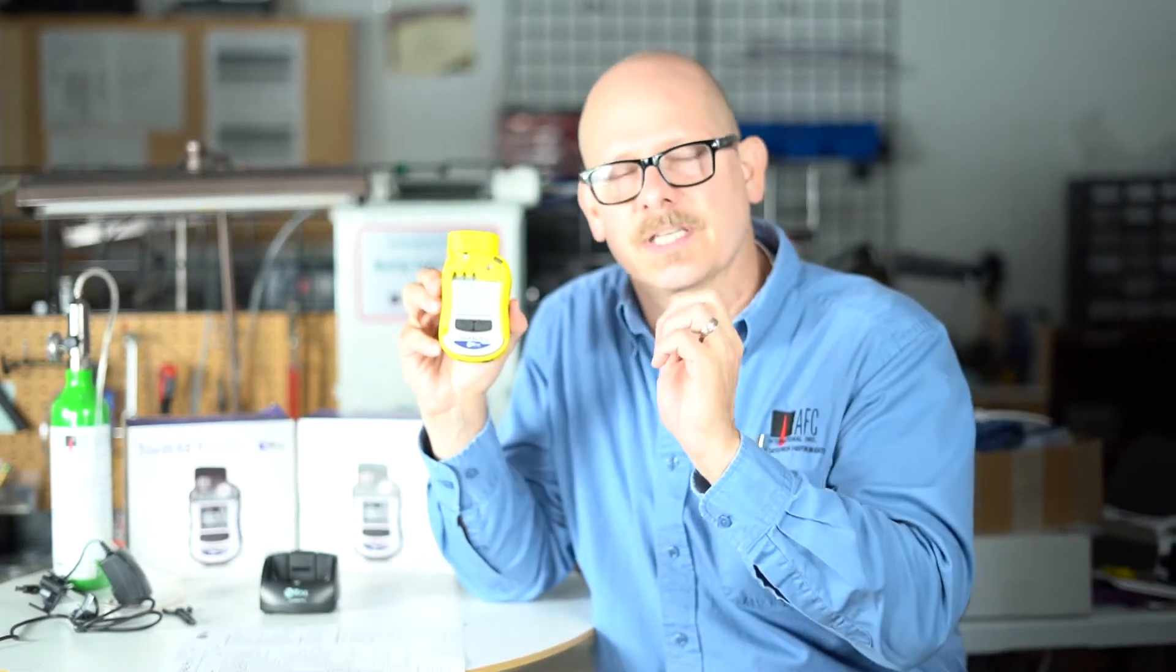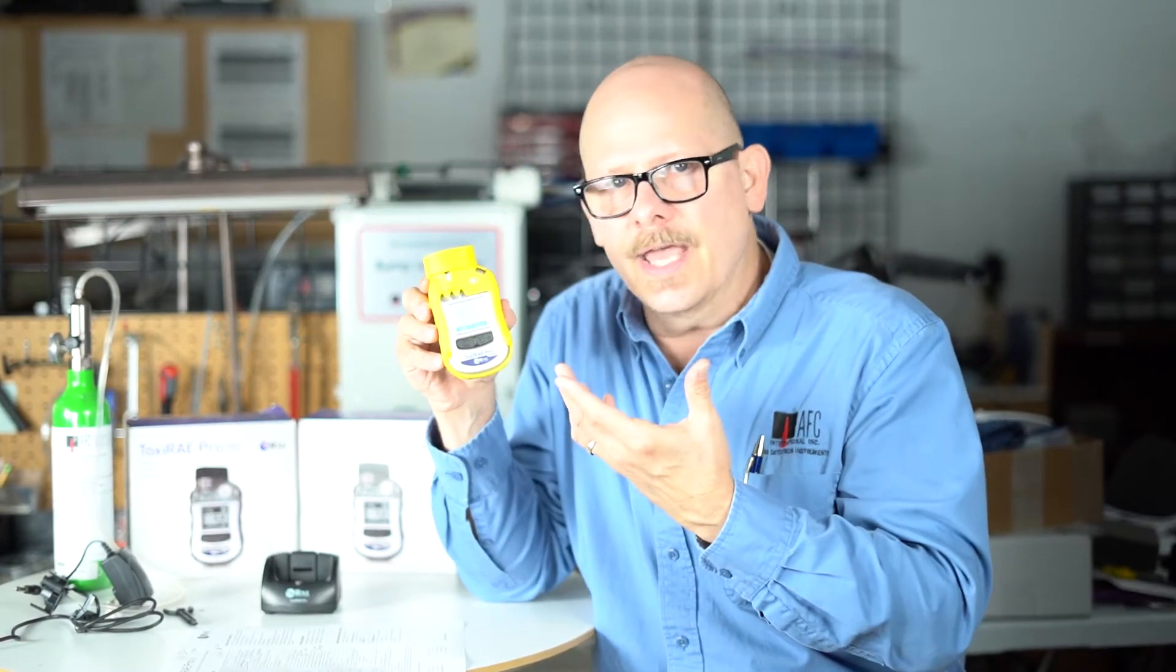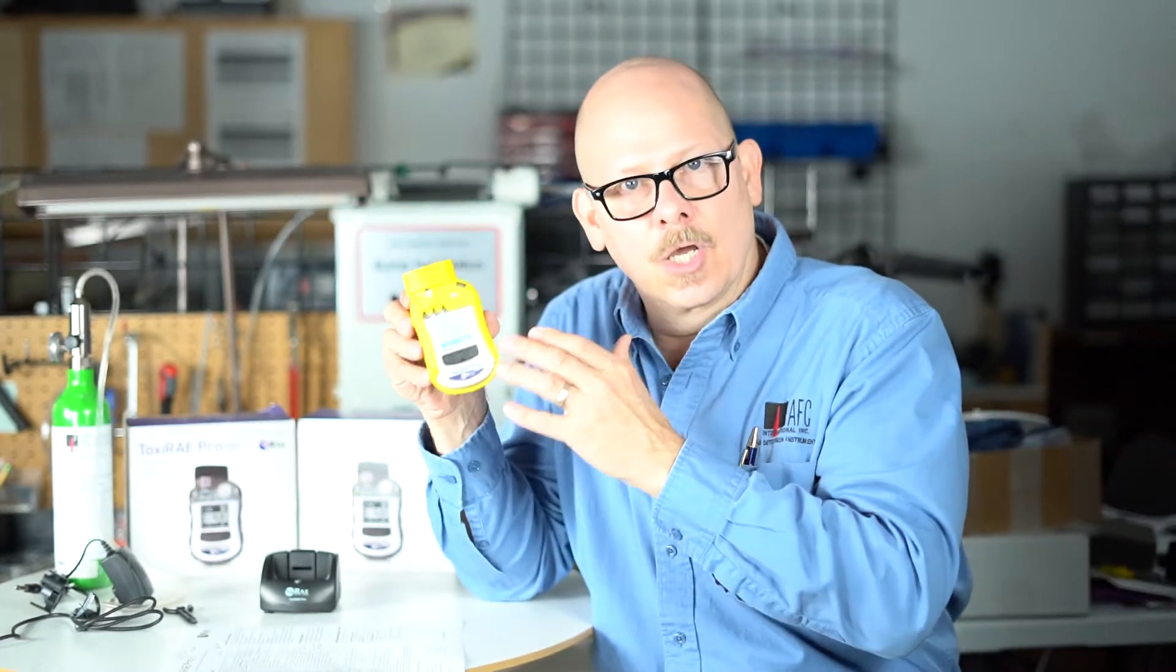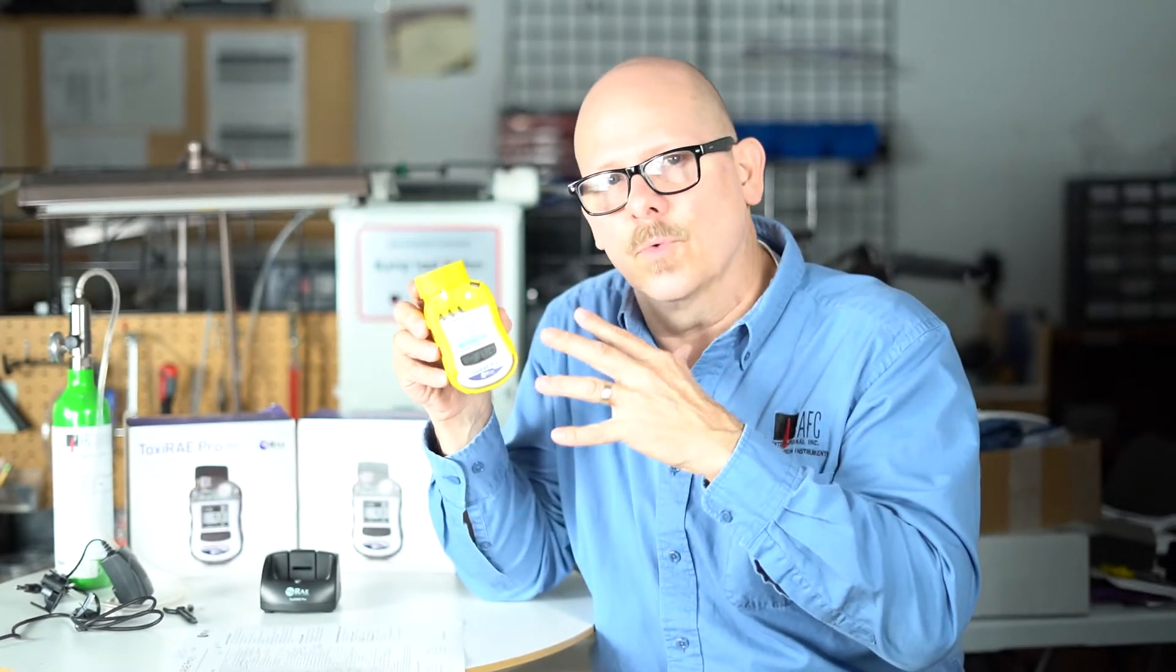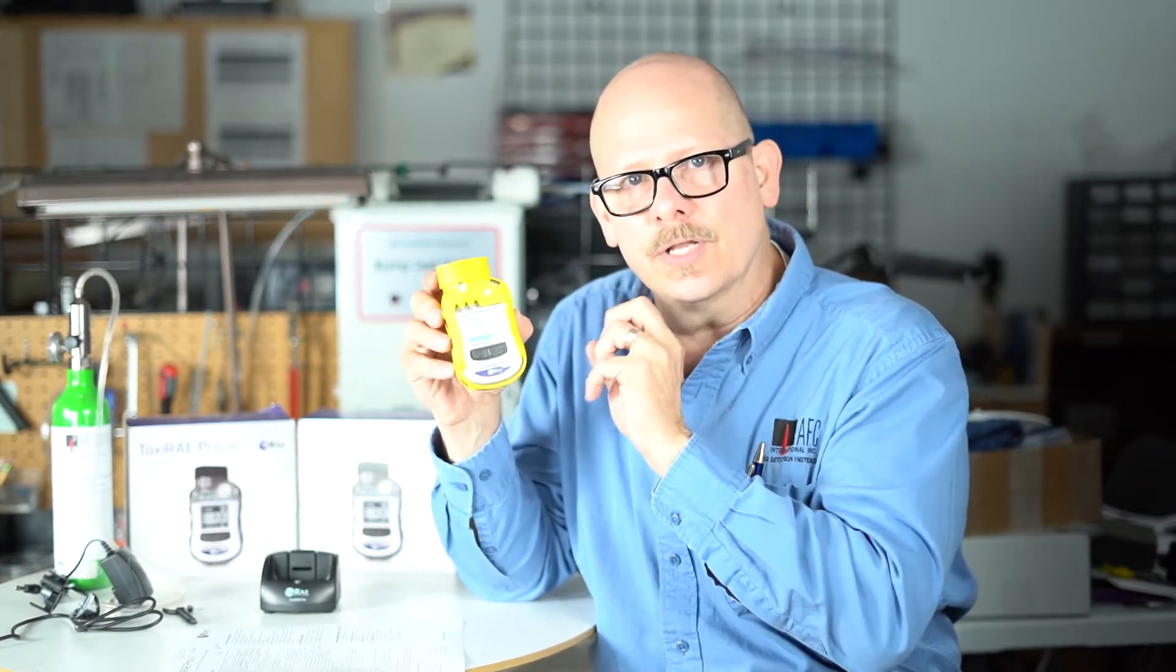The other thing you will see, it also has a time-weighted average alarm, so you can set it up for the OSHA or NIOSH or ACGIH time-weighted average PEL, and let it go off an alarm when you've reached and exceeded that. It has a light, a flash, and a vibrator alarm, so you can hear it in high noise and see it in high noise conditions.